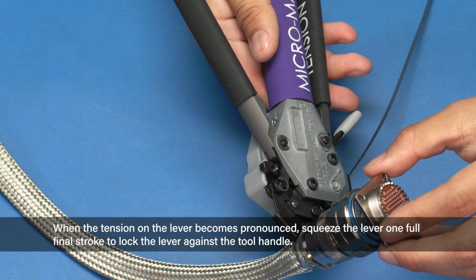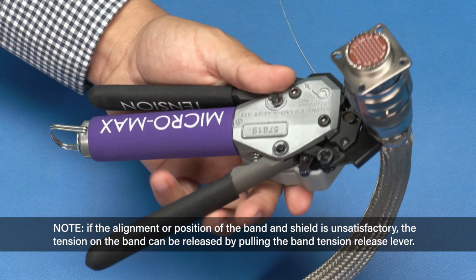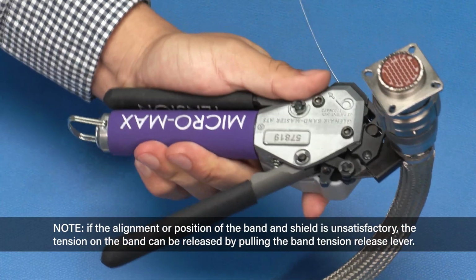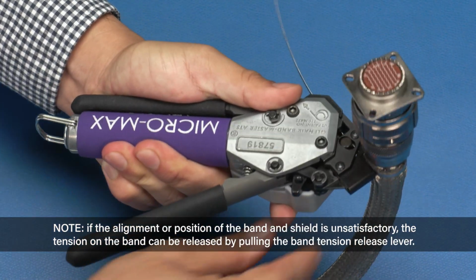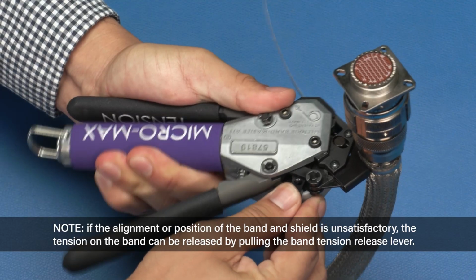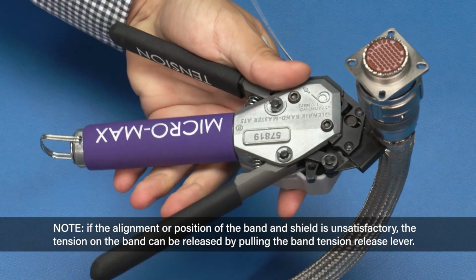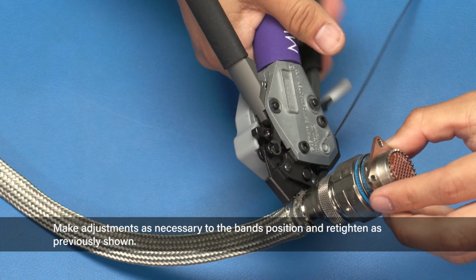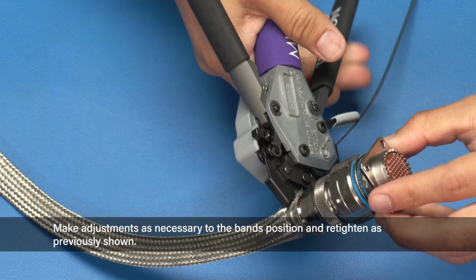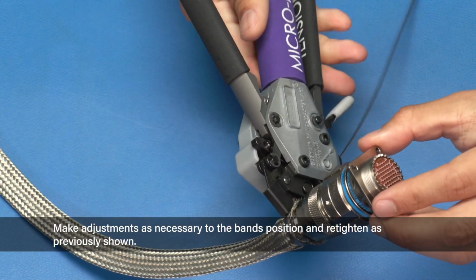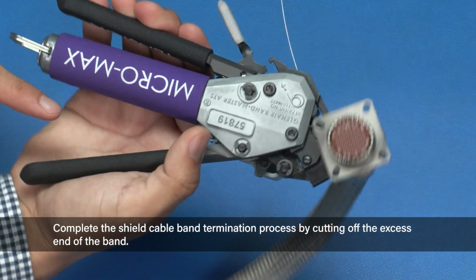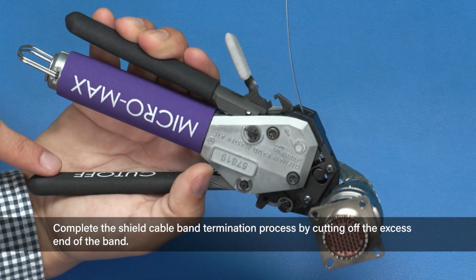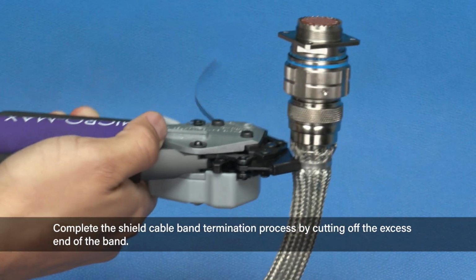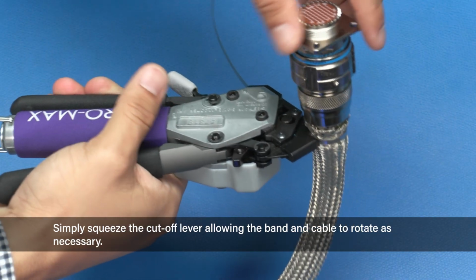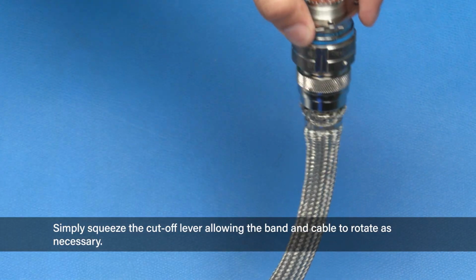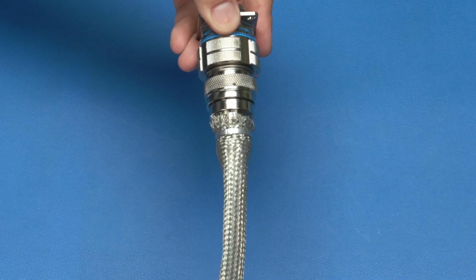Note, if the alignment or position of the band and shield is unsatisfactory, the tension on the band can be released by pulling the band tension release lever. Make adjustments as necessary to the band's position and retighten as previously shown. Complete the cable shield band termination process by cutting off the excess end of the band. Simply squeeze the cutoff lever, allowing the band and cable to rotate as necessary.